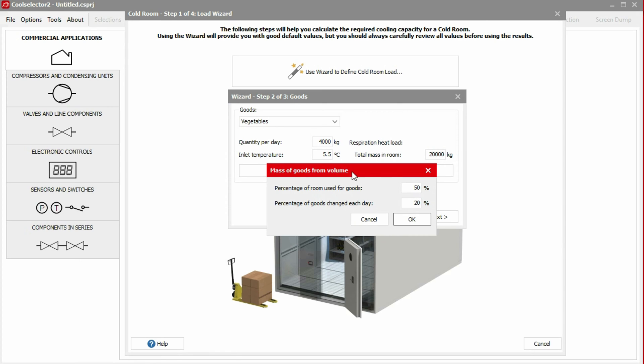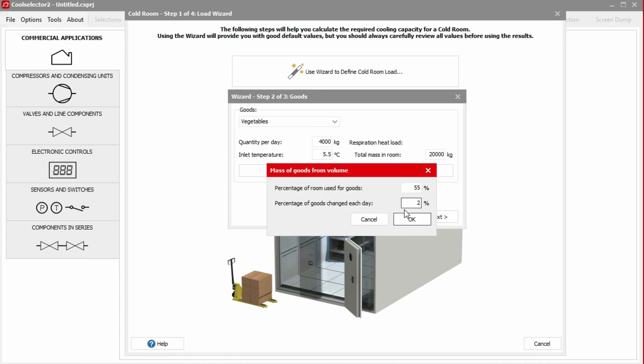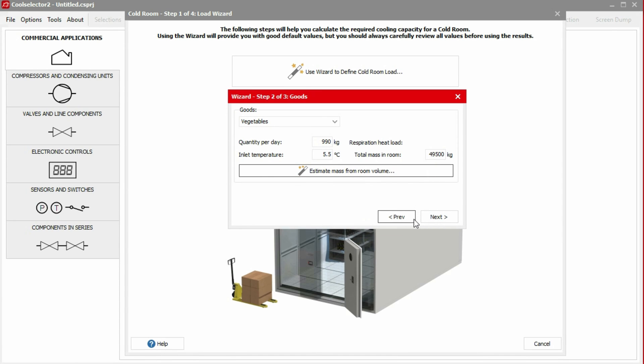We'll estimate that 55% of the room will be used for storing goods. Remember that air needs to be able to move between the goods, and people also need to be able to access these. In this example, we'll assume the goods are stored for some weeks, so the goods change each day will be fairly low. We'll assume 2%. If we now click OK, we see that CoolSelector has updated the values for us.